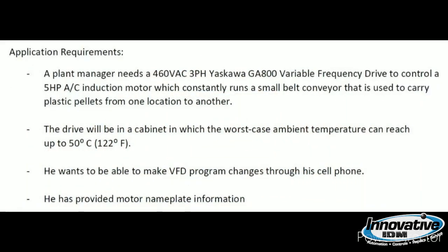I had a request from a plant manager who wanted a Yaskawa GA800 variable frequency drive. A plant manager needs a 460 volt AC three-phase Yaskawa GA800 variable frequency drive to control a 5 horsepower AC induction motor which constantly runs a small belt conveyor used to carry plastic pellets from one location to the other. The drive will be in a cabinet where the worst case ambient temperature can reach up to 50 degrees Celsius, or 122 degrees Fahrenheit.